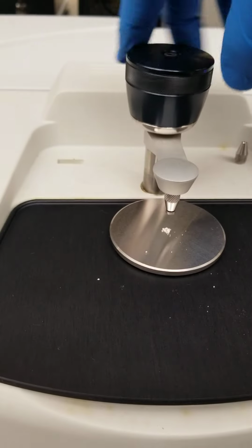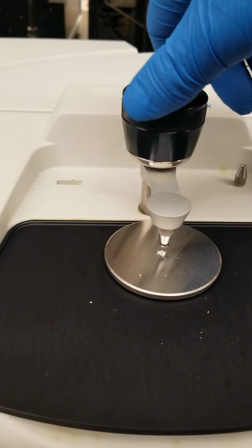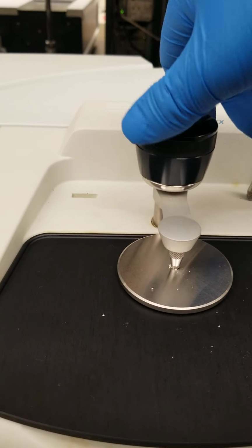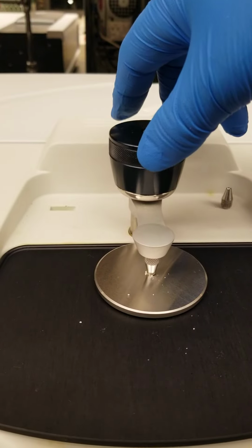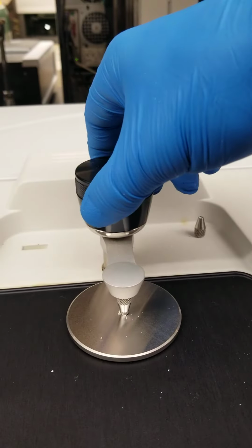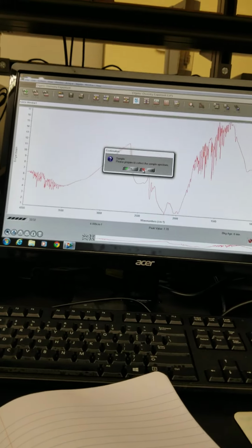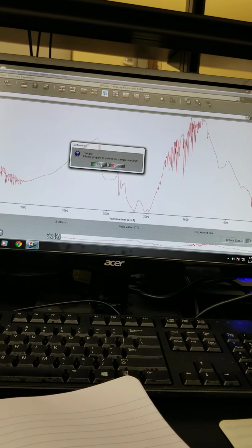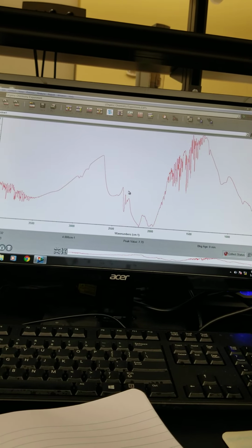Okay. Move the arm of the ATR over to the middle. Yep. It pivots. Okay. Screw it down. Clockwise. Screw it down. You're doing fine. And you'll get one snap there. It should click once when you're tight. There. All right. That's good. You can't over tighten it. It's like the gas cap. So now you say okay, because the sample is actually on the stage now.